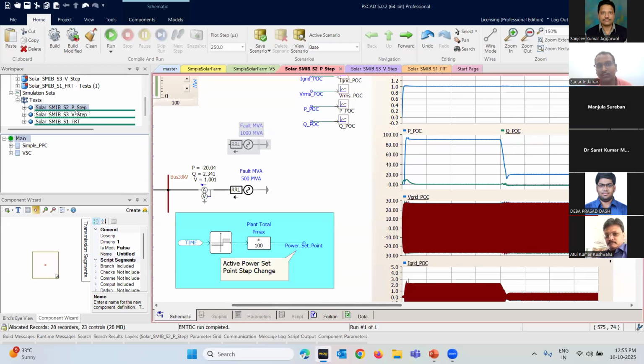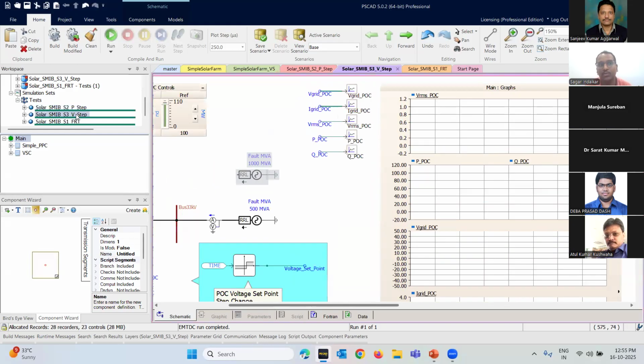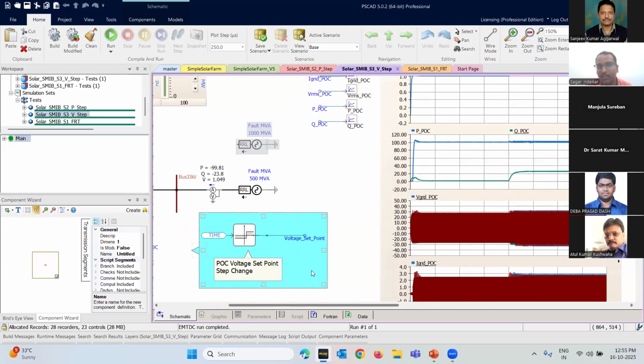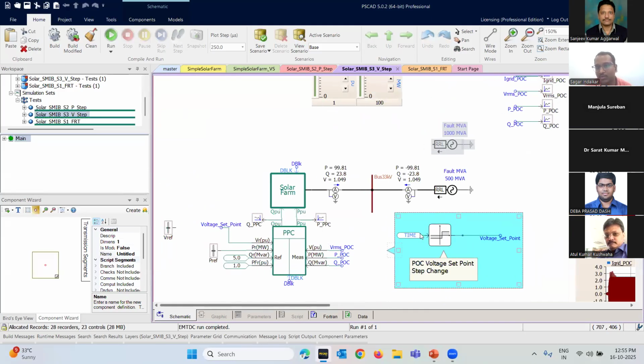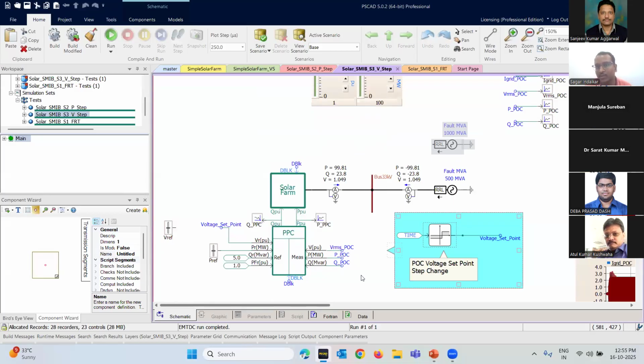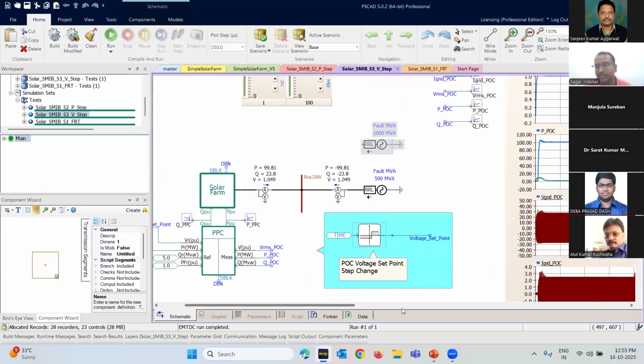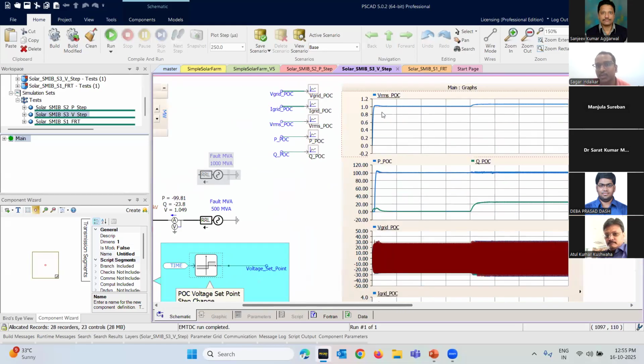Just like how you did your active power step, you have to do a reactive power step also, where you will change the reactive power set point. So here I'm changing the voltage set point. This one is for a voltage set point, and the voltage will change at 10 seconds from 1 per unit to 1.05 per unit. The voltage changes, and so does my RMS voltage. It increased from 1 per unit to 1.05 per unit.